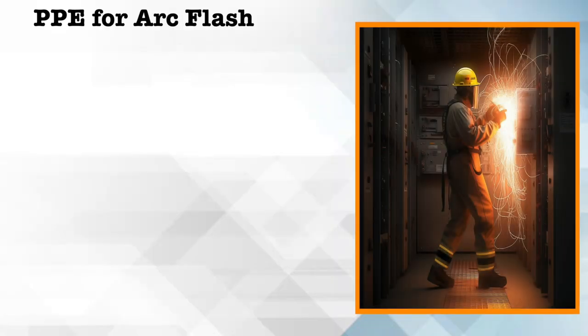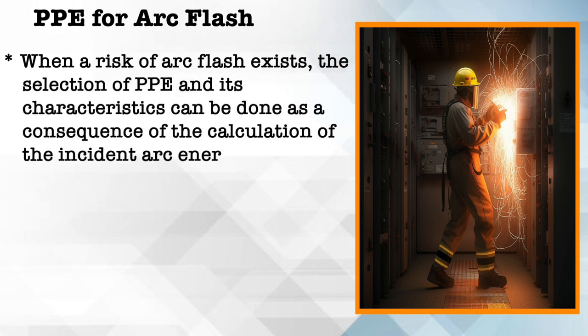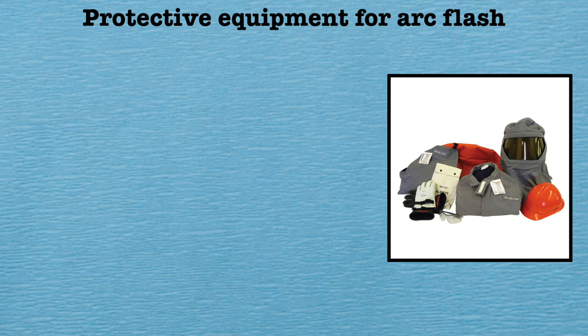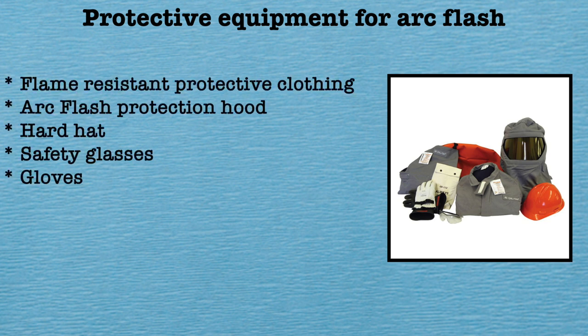For arc flash PPE — when a risk of arc flash exists, the selection of PPE can be done based on calculation of incident arc energy or by consulting a hazard category classification table, such as found in NFPA 70E (National Fire Protection Association standard 70E). Protective equipment for arc flash consists of flame-resistant protective clothing, an arc flash protection hood, hard hat, safety glasses and gloves.